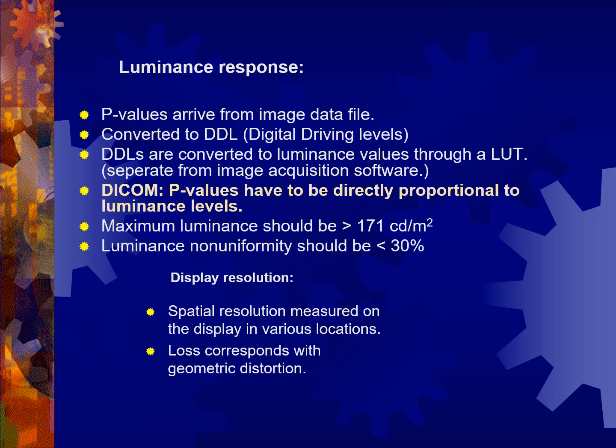Now, you have to know this part for the registry. DICOM says that the adjusted LUT values, which are called the p-values from the image data file, when they're converted by the driving software for the display to the digital driving levels, must be a 1-to-1 directly proportional conversion.